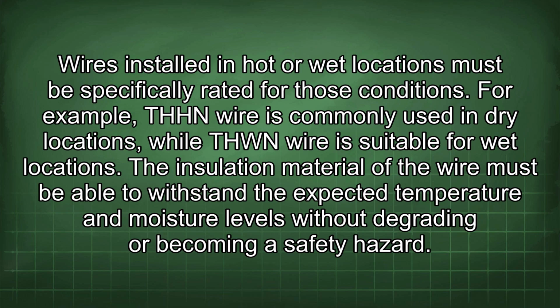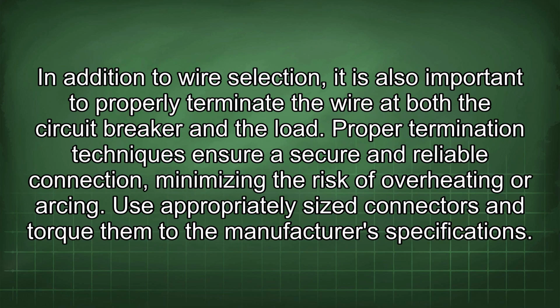In addition to wire selection, it is also important to properly terminate the wire at both the circuit breaker and the load. Proper termination techniques ensure a secure and reliable connection, minimizing the risk of overheating or arcing. Use appropriately sized connectors and torque them to the manufacturer's specifications.